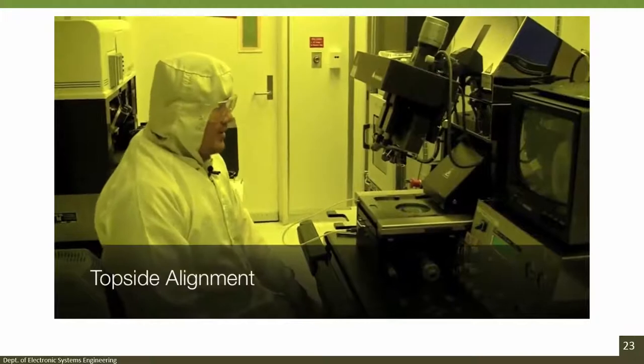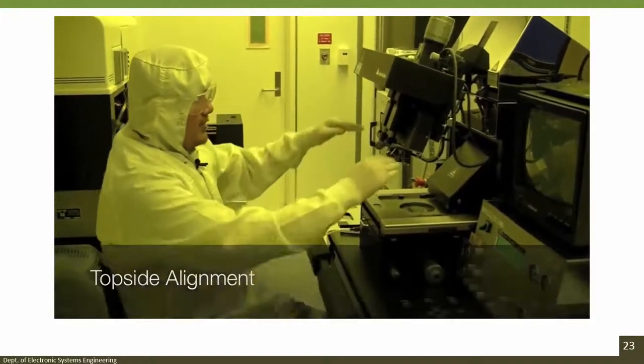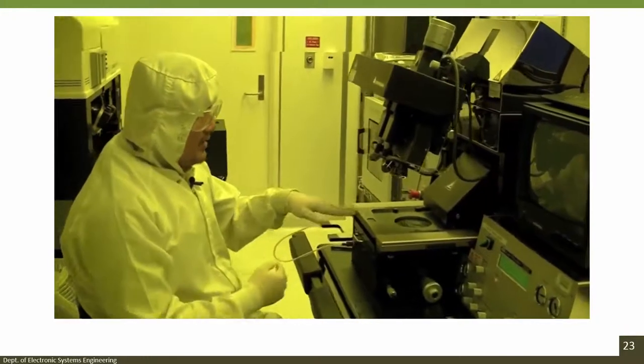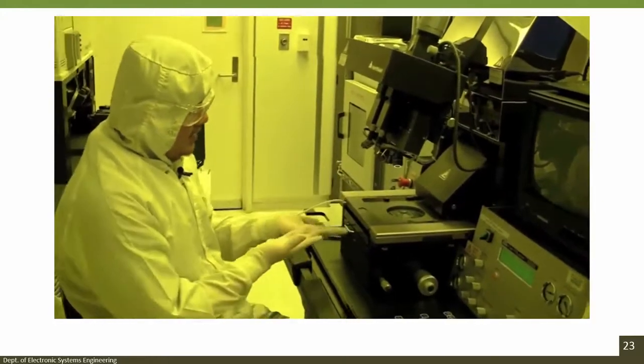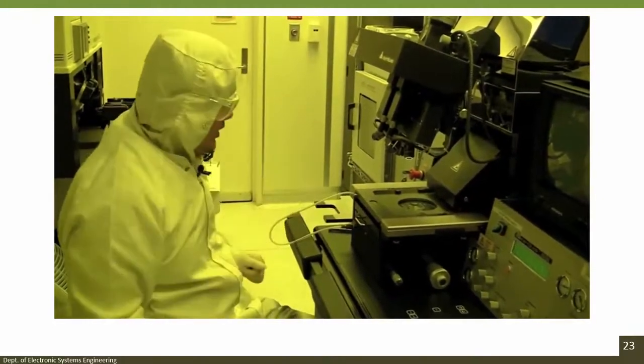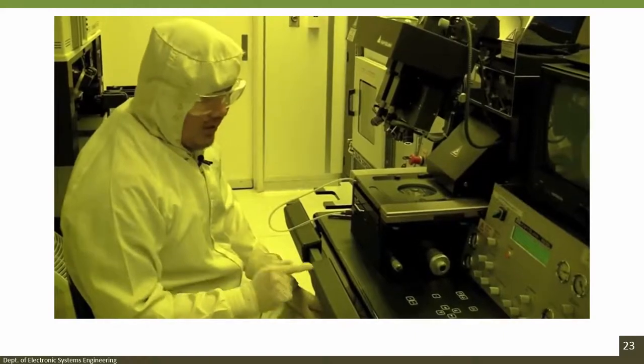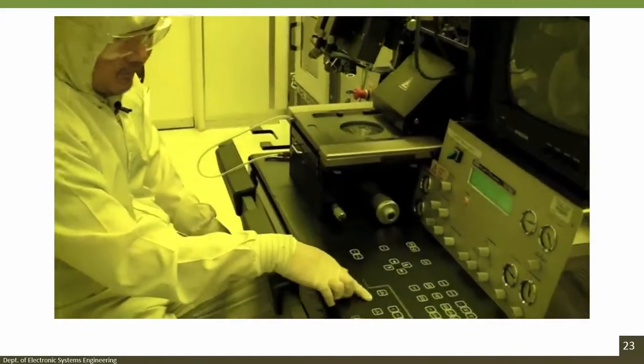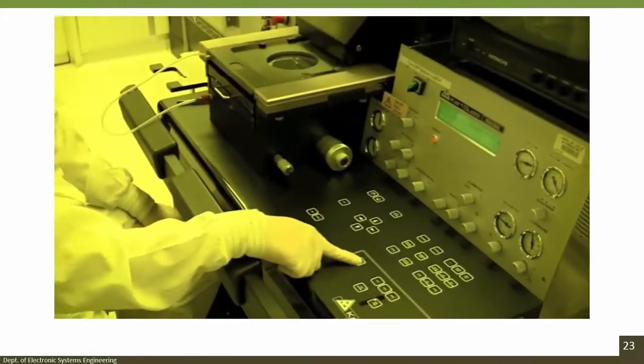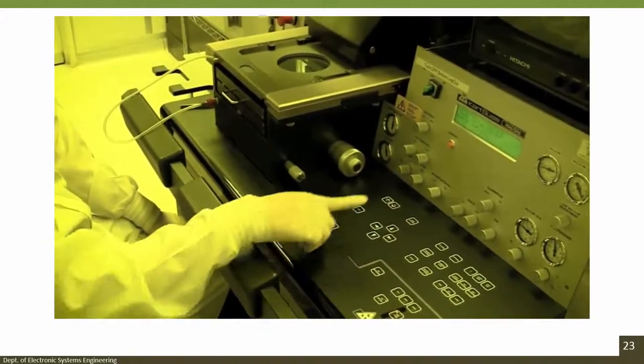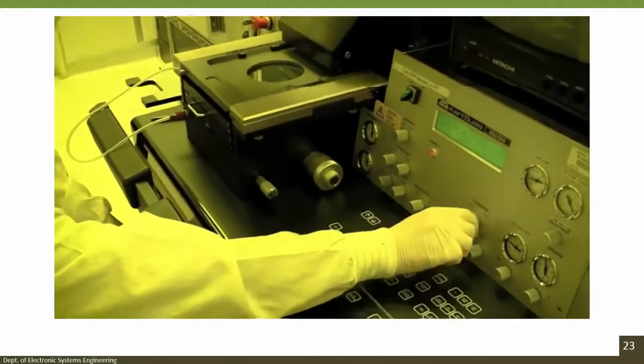What we're going to do now is topside alignment, using the microscope on the top to align to the wafer that's underneath through the glass. To do topside alignment, we need to remove the backside microscope. So we press this button. That turns it off. Also, we need to put the illumination to the top side.